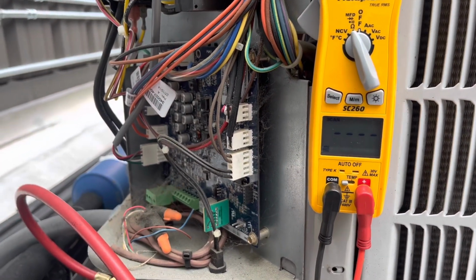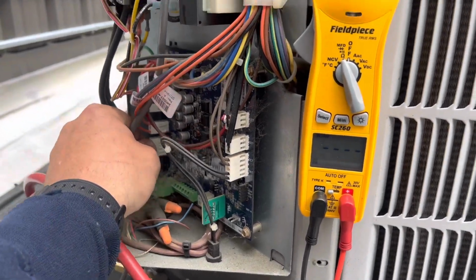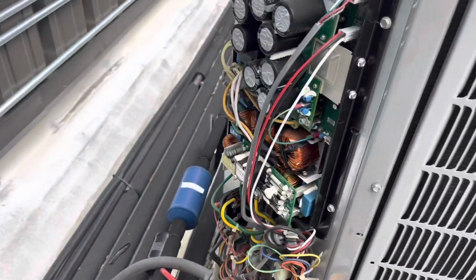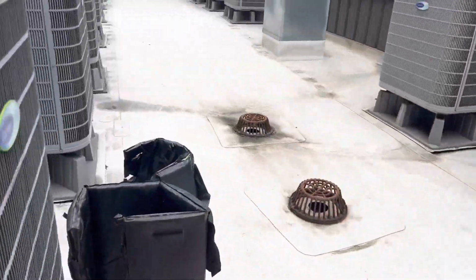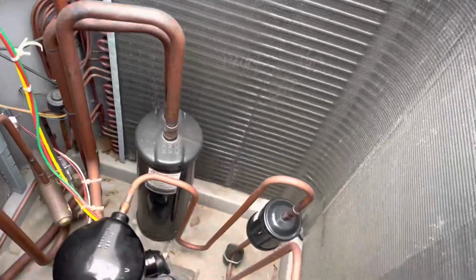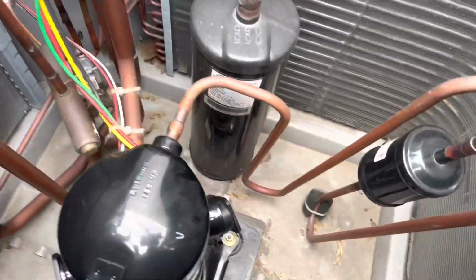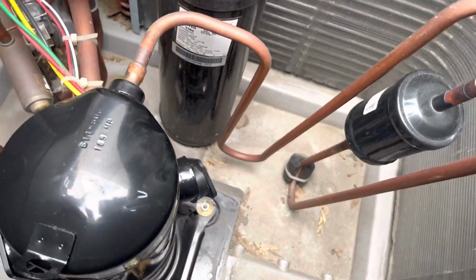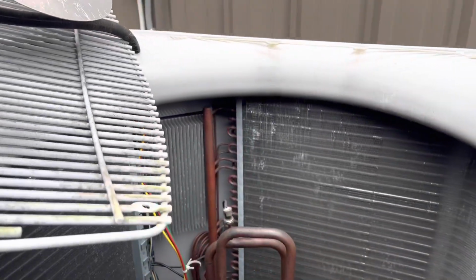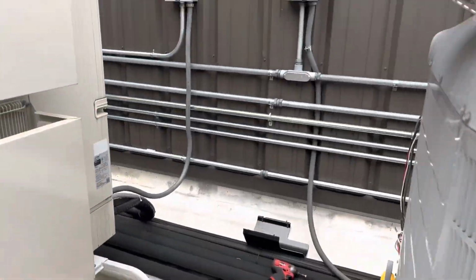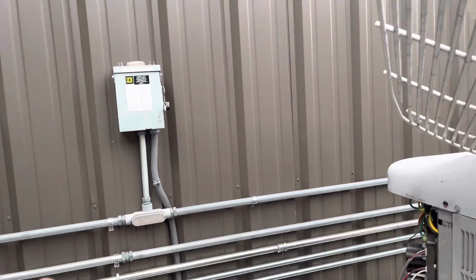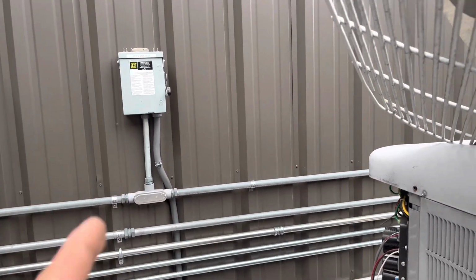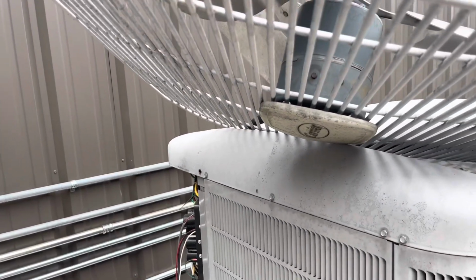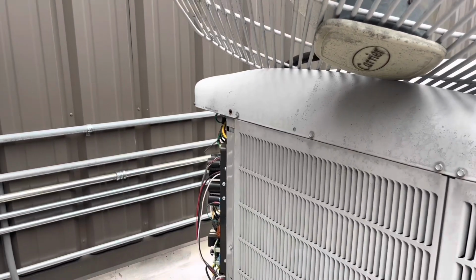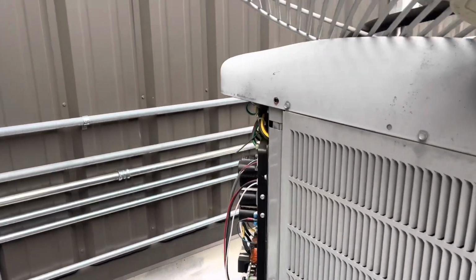So what I'm going to do now is just for kind of a little cheat, I'm going to keep this unplugged here, where I have my connection unplugged there. I'm going to put this fan back on. Then I'm going to go downstairs after I power this up and call for heating or cooling and see if my error code changes. And it should. If it doesn't, then I know it's probably just the board alone.